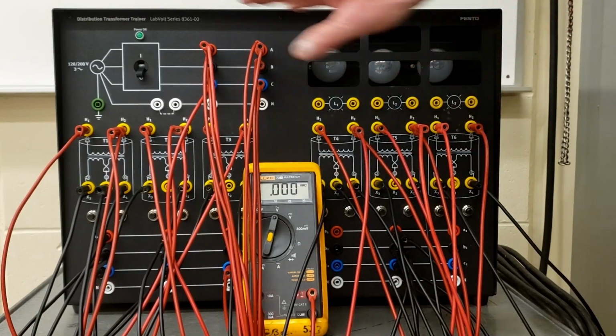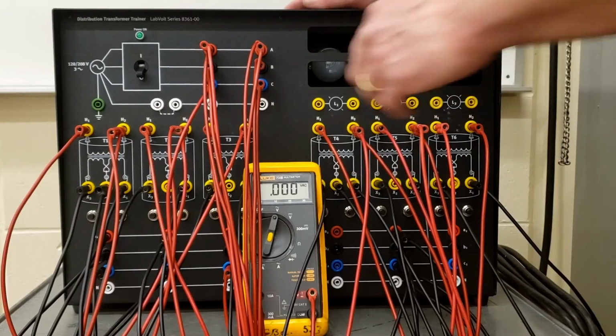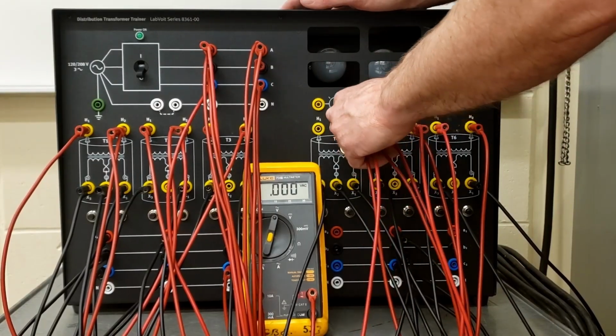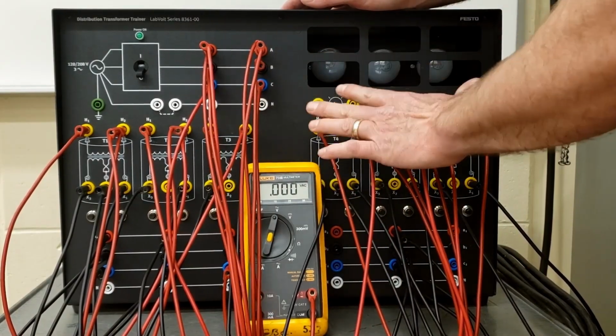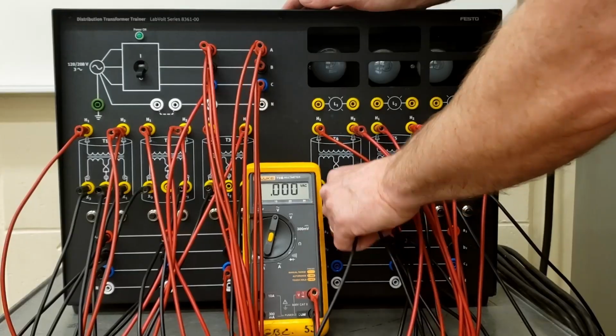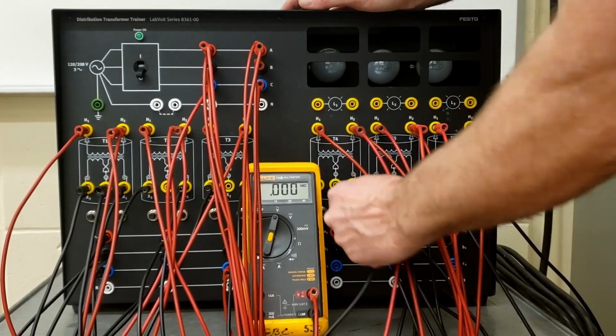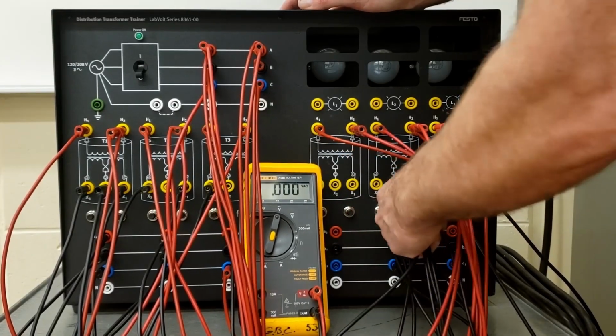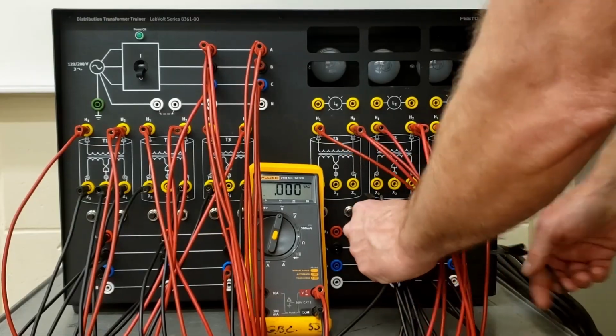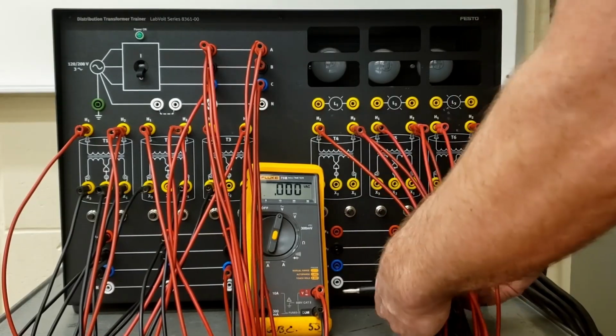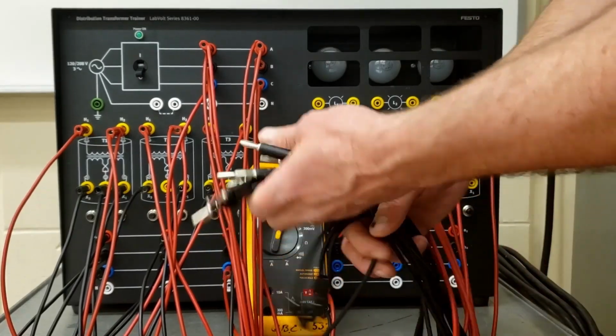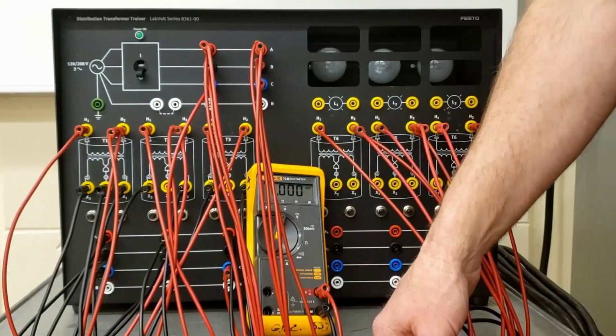Now turning it off, we're going to remove all of these terminals here. No, not the primary - the primary is staying the same, it's the secondary that's changing. So you've got to make sure the power is turned off because you're quickly removing leads. Shrouded leads would be best for these guys.